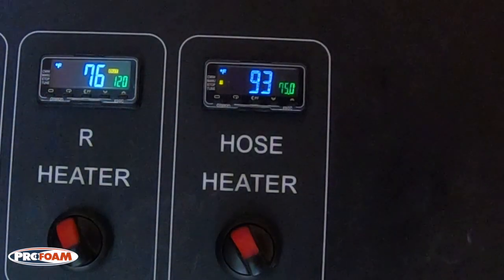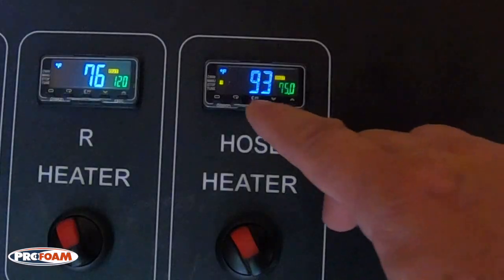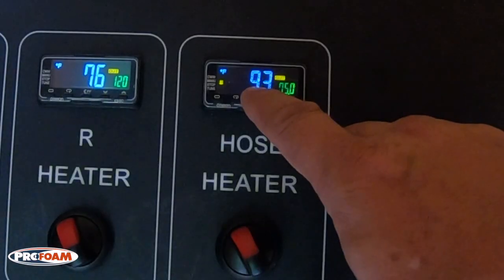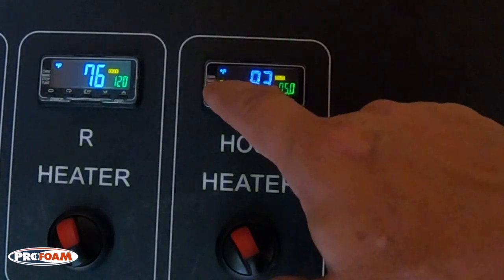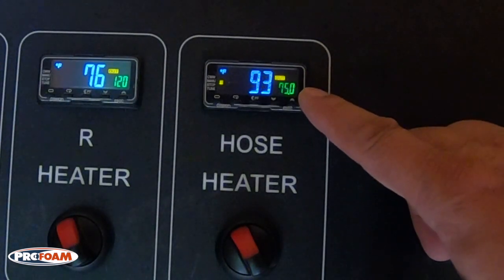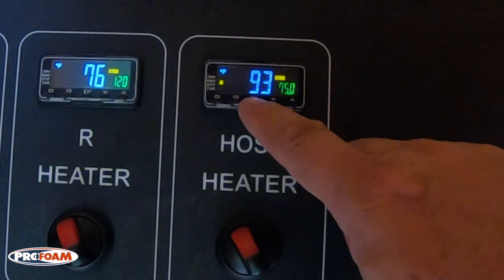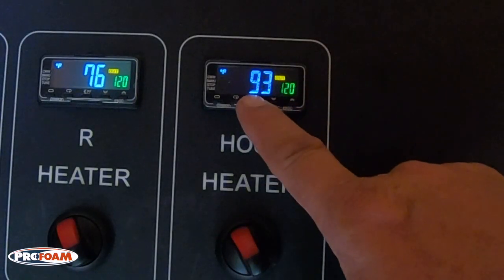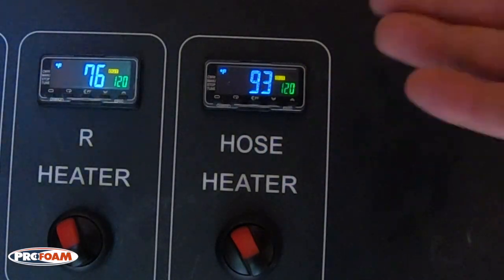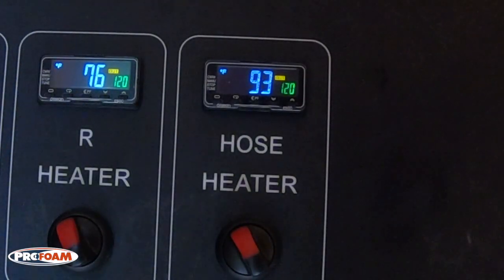So once you're done and get your repair done, you can go back in and set it back to regular hose heat mode and let the controller do the work. Once you have your issue resolved, that's either the purple wire has been repaired or replaced, or the sensor has been replaced, then we want to go back out of manual hose heat mode. But you'll see that just by doing the repair, this went back to a number instead of the error. But this is showing us, and that little light there, that this is still in manual hose heat mode. To go back, all we need to do is hold that button until this goes back to our set point right there. That will function like it used to when it was in regular hose heat mode, ready to go.